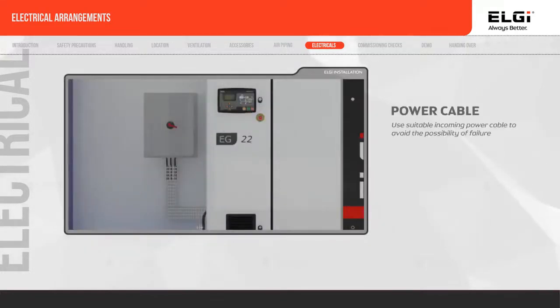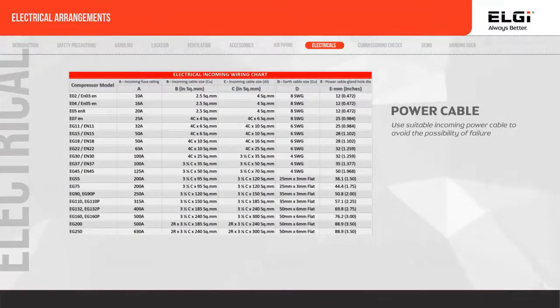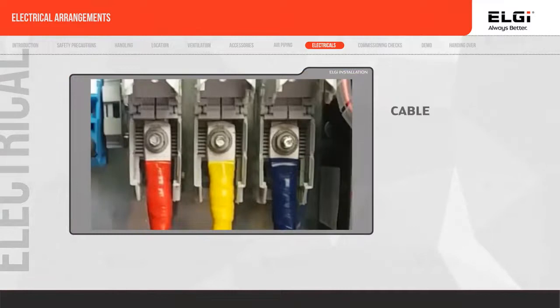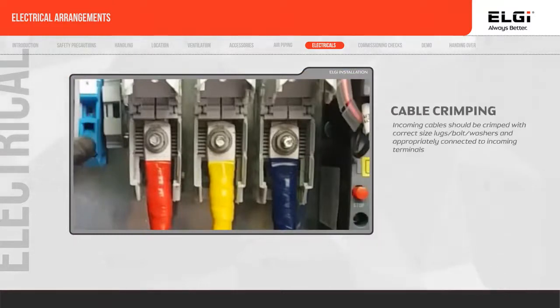Use suitable incoming power cable to avoid the possibility of failure. Use the incoming cable reference chart. Incoming cables should be crimped with correct size lugs, bolt, washers, and appropriately connected to incoming terminals.